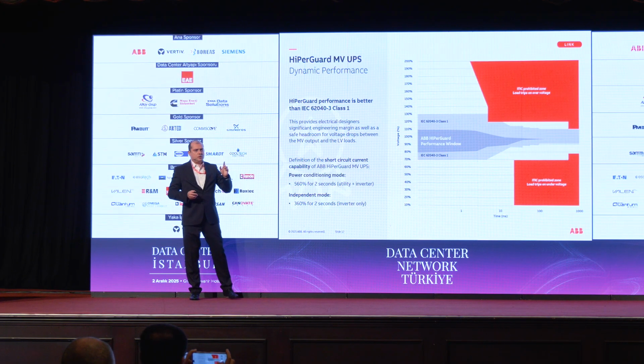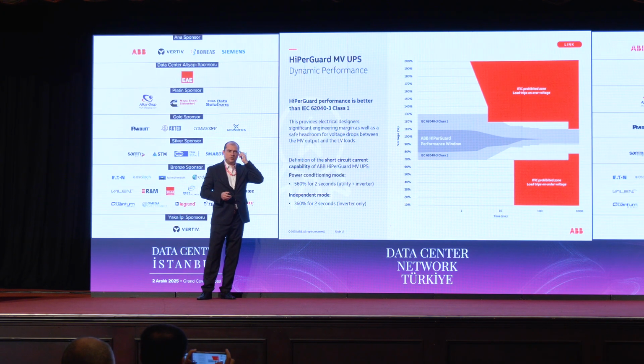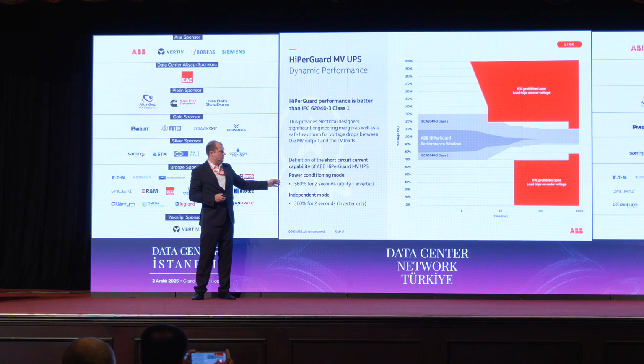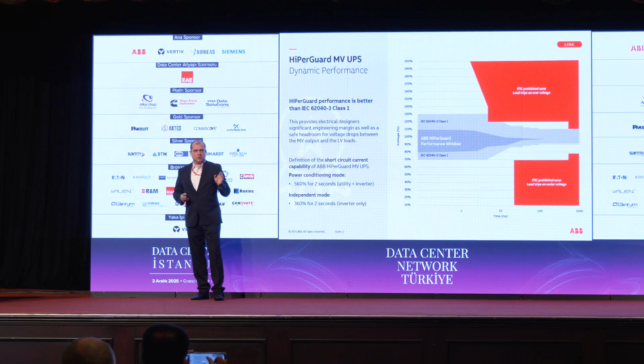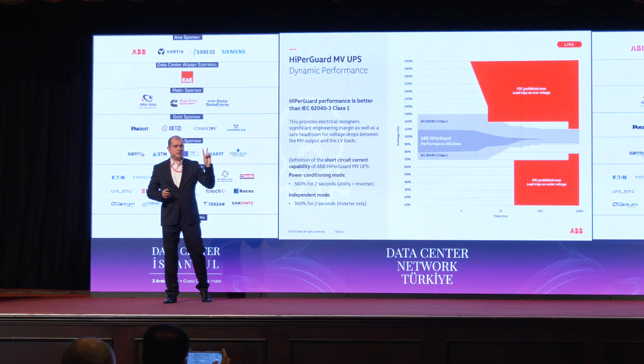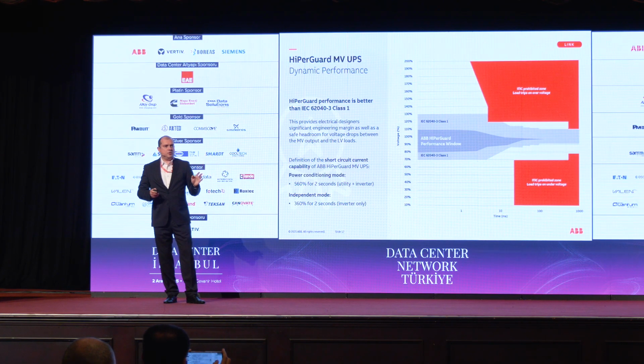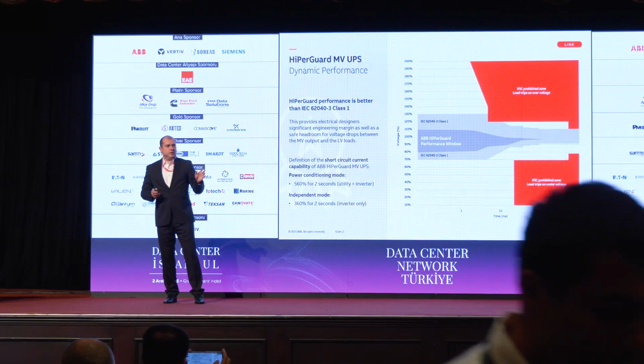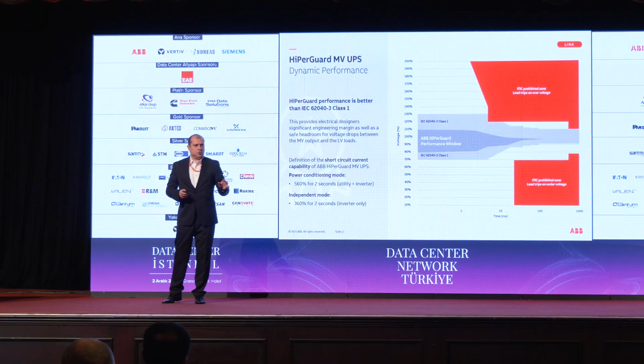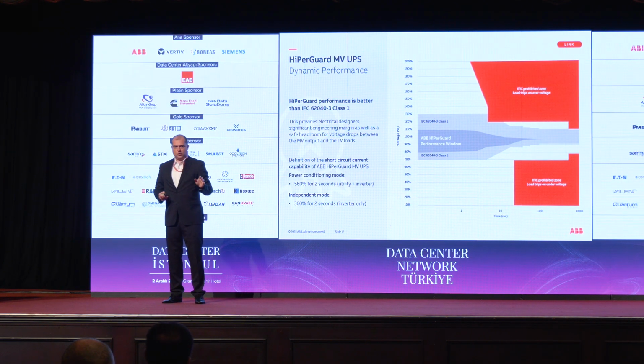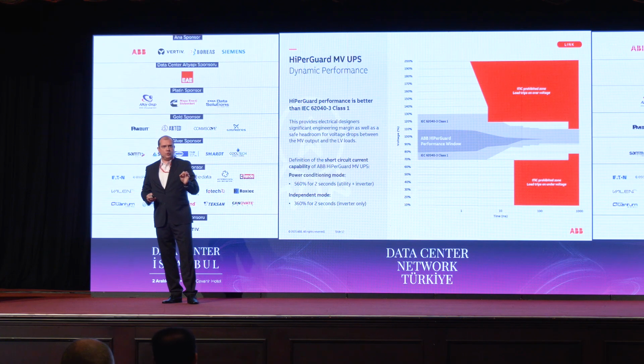Also, if we want to clear the faults, we need to have a huge amount of short circuit capability, and we can deliver up to 360% of the nominal current for a period of up to 2 seconds. This is important because we don't need to trip all of the circuit breakers so quickly. We can hold, and we never drop the load.